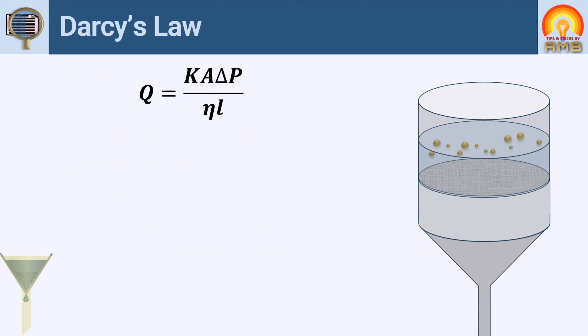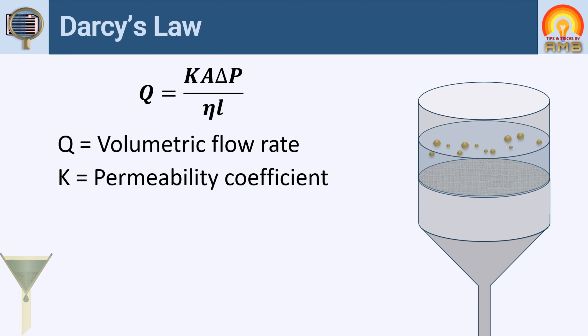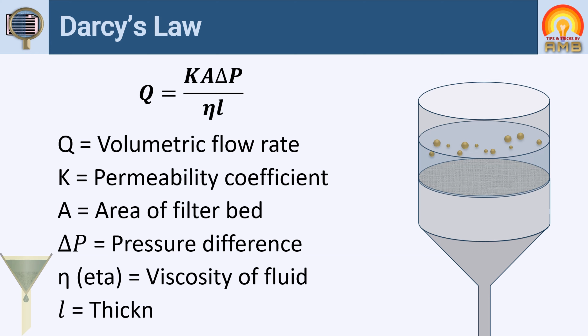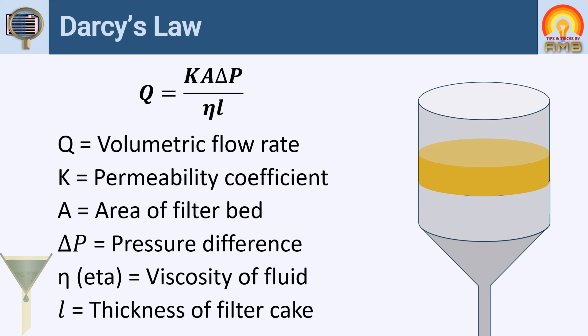This is Darcy's equation, where Q is volumetric flow rate, K is permeability coefficient, which depends upon the nature of the precipitate to be filtered and the filter medium, A is the area of the filter bed, delta P is the pressure difference on the liquid and below the filter medium, eta is the viscosity of the fluid, and L is the thickness of the filter cake.